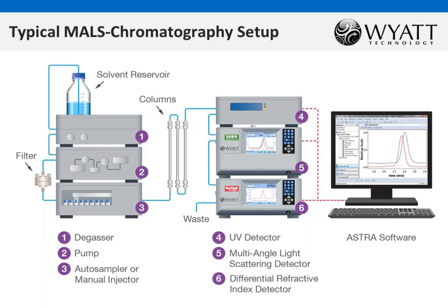Note that this particular setup contains two concentration detectors, a UV-Vis and a DRI. A second concentration detector may be used to confirm the measured concentrations, compute sample or detector response, or analyze protein conjugates or copolymers.